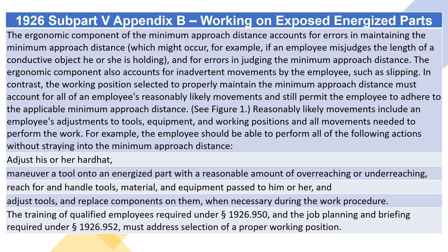Working positions selected to properly maintain the minimum approach distance must account for all of an employee's reasonably likely movements and still permit the employee to adhere to the applicable minimum approach distance. Reasonably likely movements include adjustments to tools, equipment, and working positions, and all movements needed to perform the work — for example, adjusting a hard hat, maneuvering a tool onto an energized part with reasonable overreaching or underreaching, reaching for and handling tools, material, and equipment passed to the worker, and adjusting tools and replacing components when necessary. The training of qualified employees under Section 1926.950 and the job planning and briefing under Section 1926.952 must address selection of a proper working position.